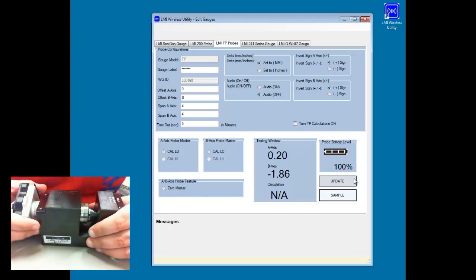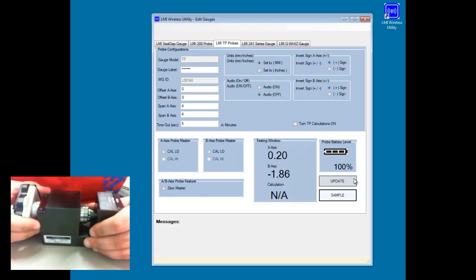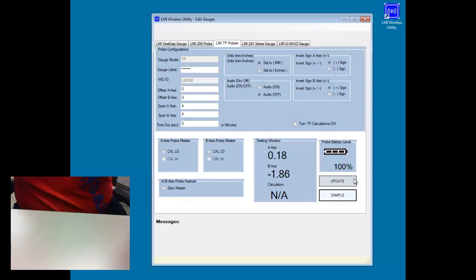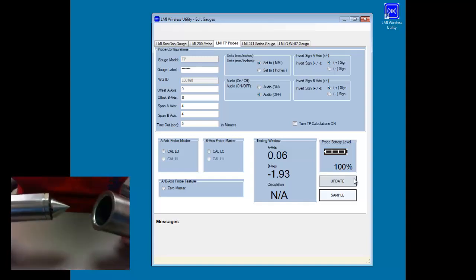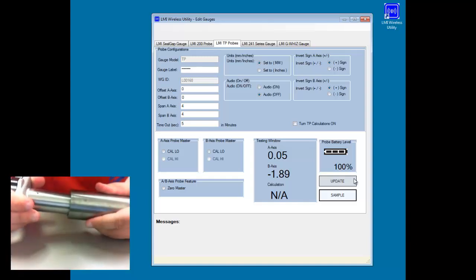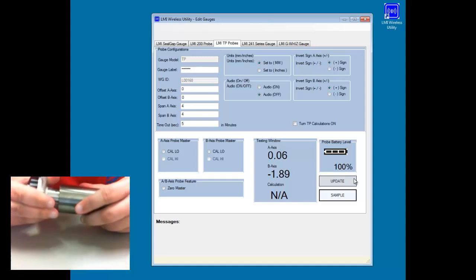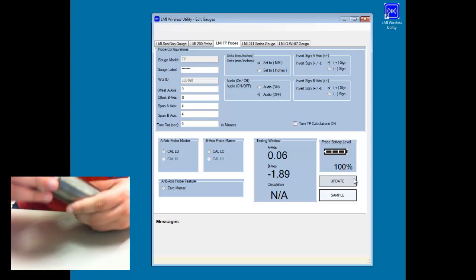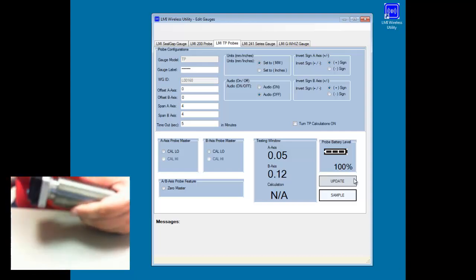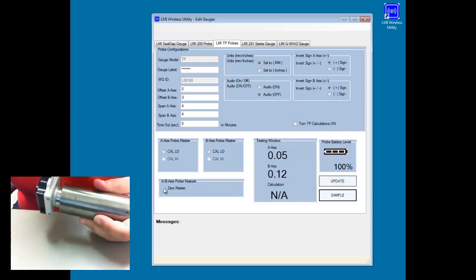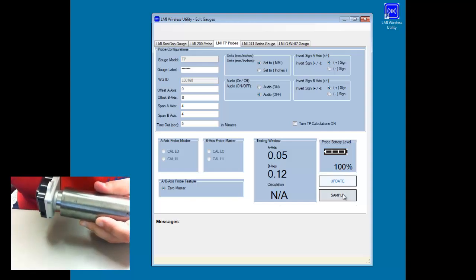So now I need to zero this probe out. To do that, I'm going to pull this out of here. I'm going to get the master bushing. Slide the probe all the way in. Click on the zero master function here. And then sample this.